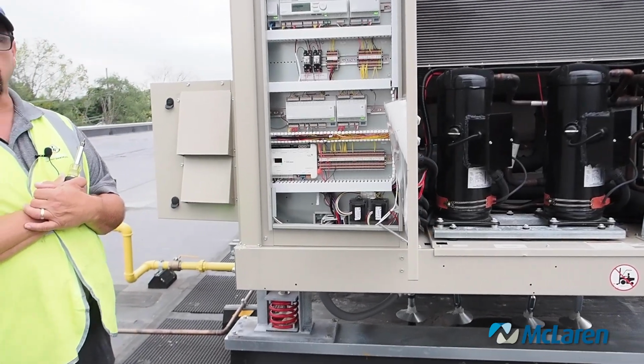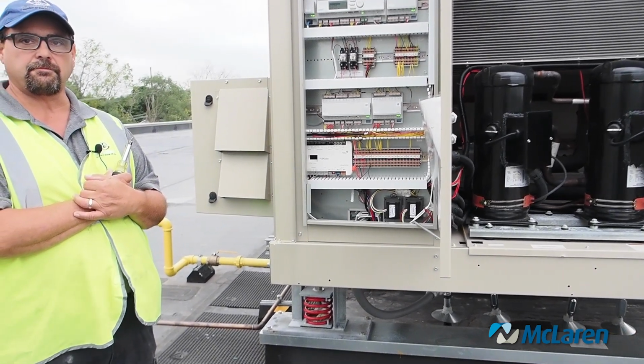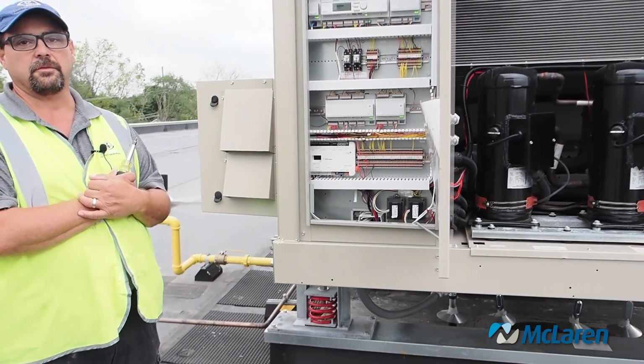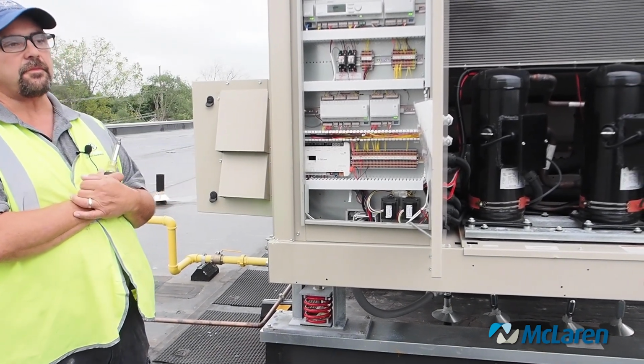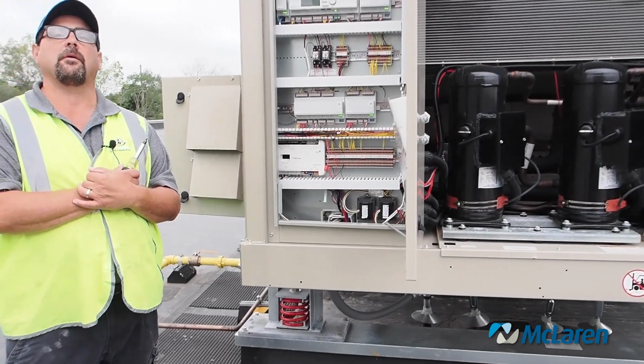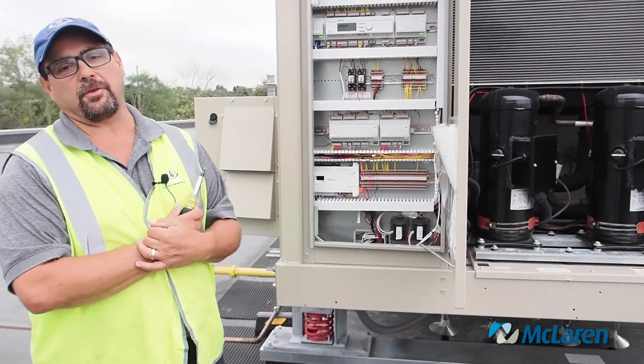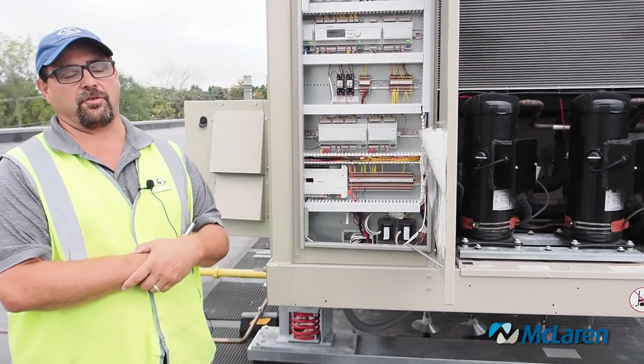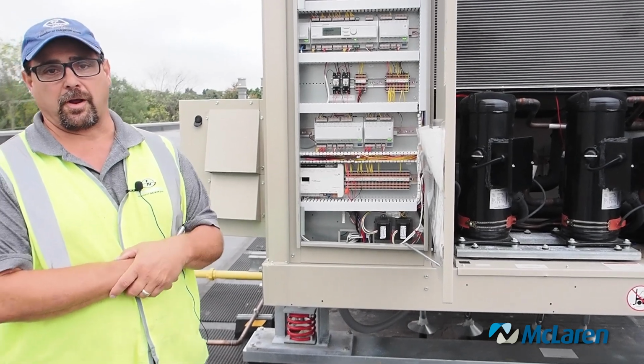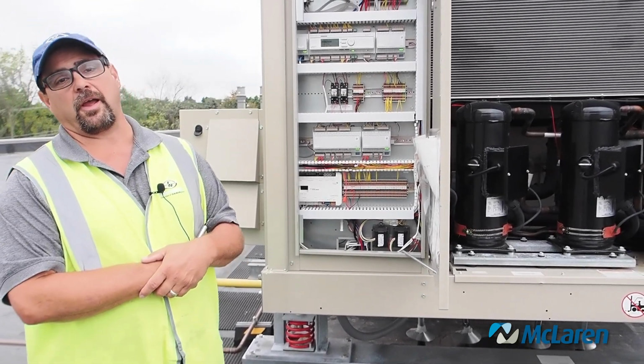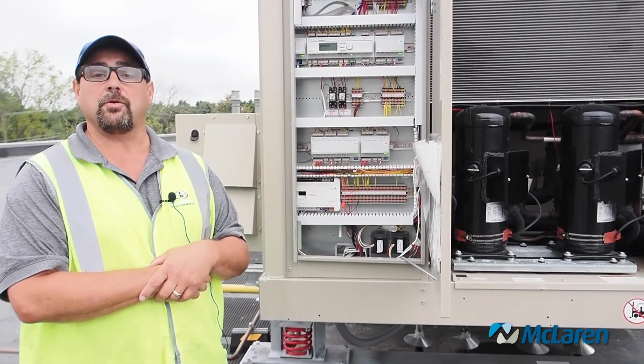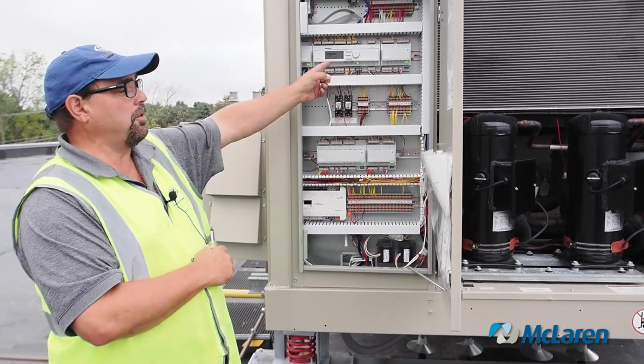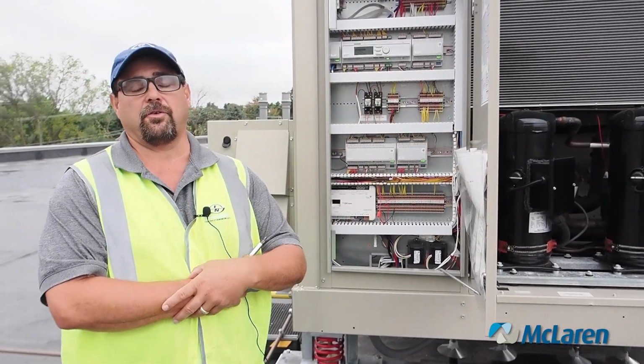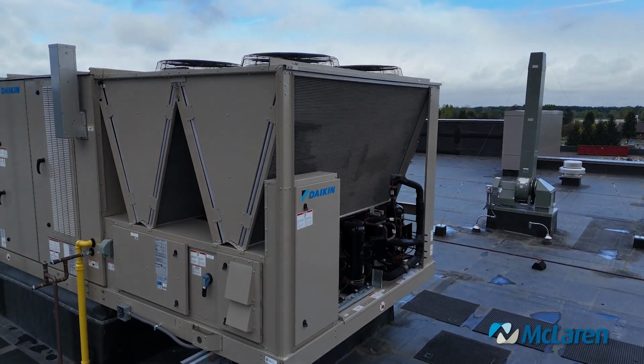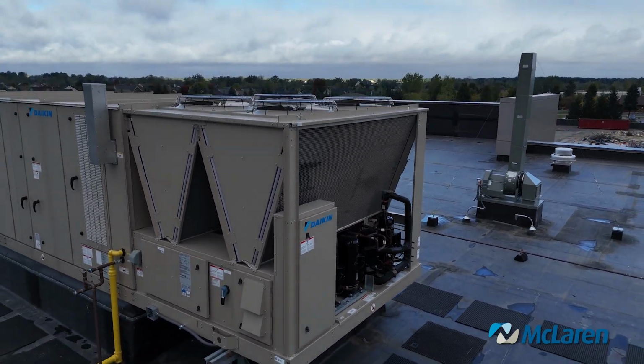Around the corner, you mentioned there's a box covered that they will never have to take off. What kind of error indicators would require them to recognize that the problem's in that box? If you have a problem inside the inverter control box, the symptoms of that would be inverter compressor alarms, your condenser fans not operating, non-communication between the main controller and the inverter board. There's a whole variety of alarms that could be generated from that inverter section.